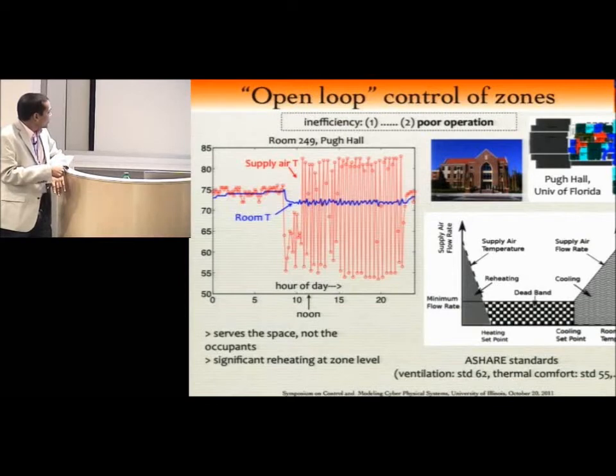So if you have to get one conclusion out of this, it's that this control system, as it is operated now, is serving the space, not the people, not the occupants, right? And we don't need to serve the space, space exists for the occupants. The other problem is there's a significant amount of reheating tied to the way things are operated, and this is, I think, for a summer day in Florida. You don't need to reheat anything, but you have to because of the way you're doing things.